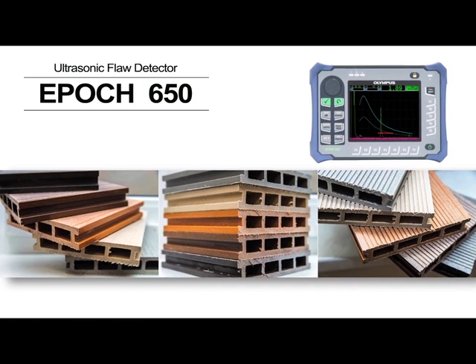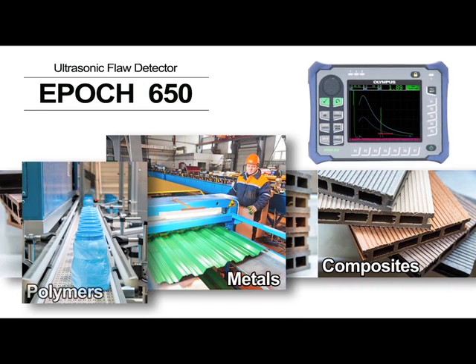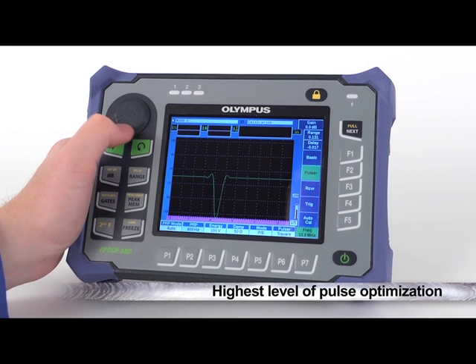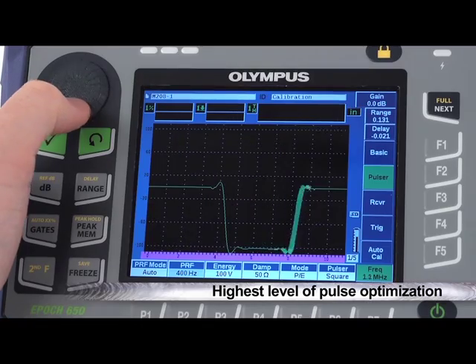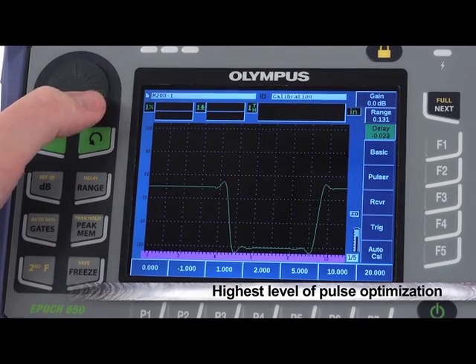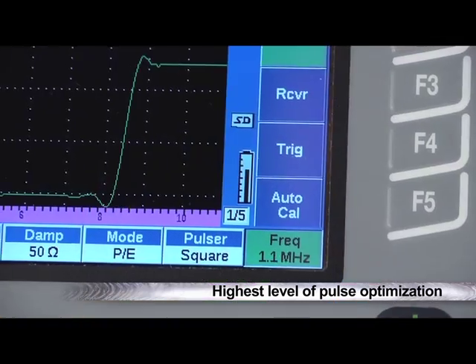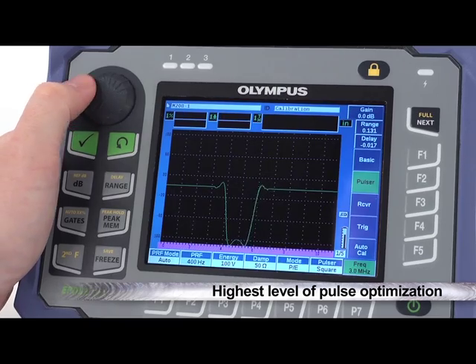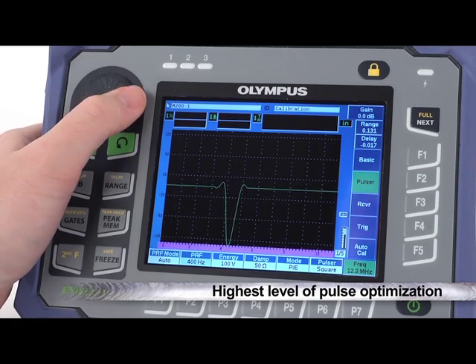Ultrasonically, the EPOCH 650 is flexible for a wide variety of applications, including metals, composites, and polymers. It features much finer pulse width control than previous generation EPIC instruments, allowing for the highest level of pulse optimization we've ever offered. This benefits both precision applications for thin materials and small flaws, as well as high penetration applications using low frequency transducers.